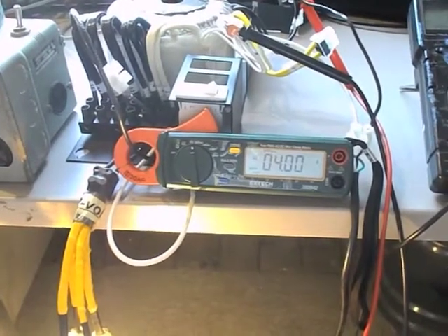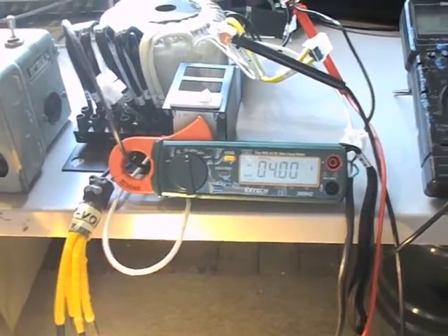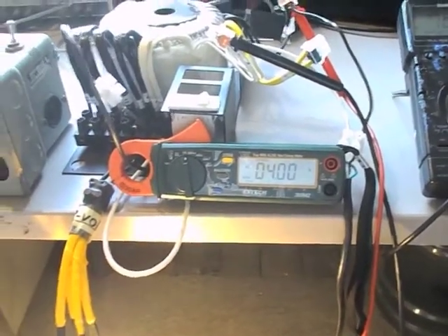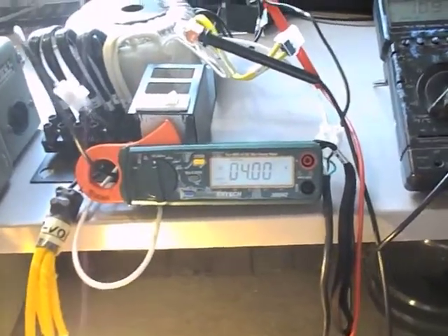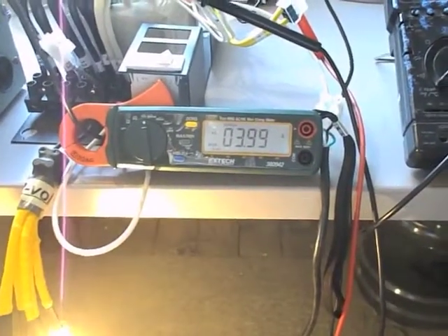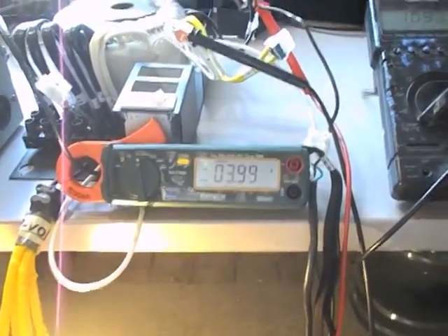Now, the National Electric Code references another general rule of thumb, which is a 20% derating. So instead of 60 watts, we just have a single 50 watt lamp, which is 4 amps on a 5 amp breaker.